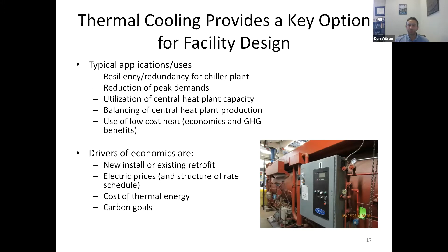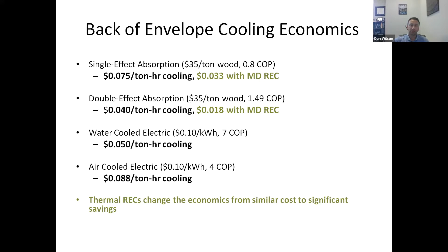To give you an idea of the economics: the first two lines are absorption chiller machines with different thermal temperatures, showing the cost per ton hour for cooling using a wood energy system. The next two are different approaches using electric machines for cooling, showing the cost per ton hour. The wood systems are on par with or possibly save a little on the cost of cooling at these wood and power prices. What can change this pretty dramatically again is the thermal REC, since that's such a substantial portion of wood chip delivered heat cost - factoring that in gives some nice savings for cooling with thermal chillers, especially at large facilities.